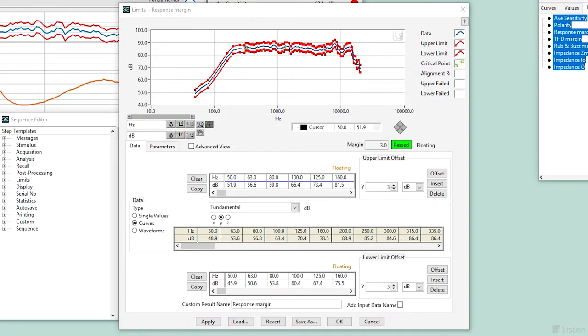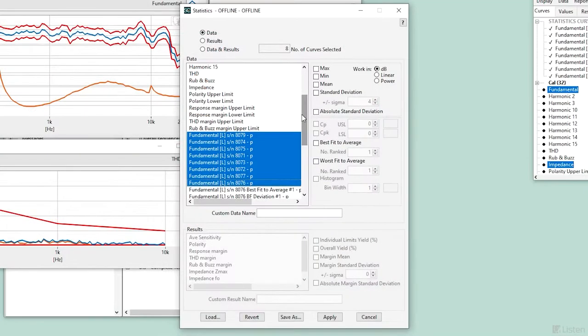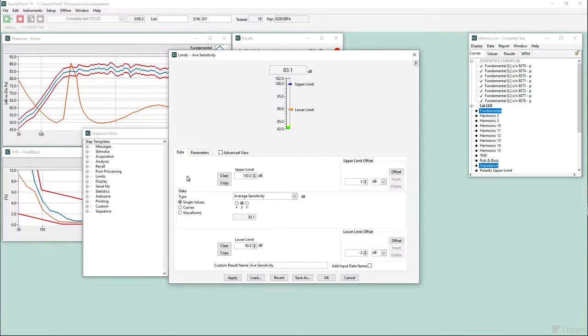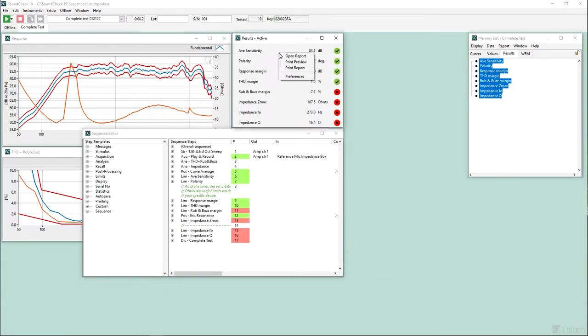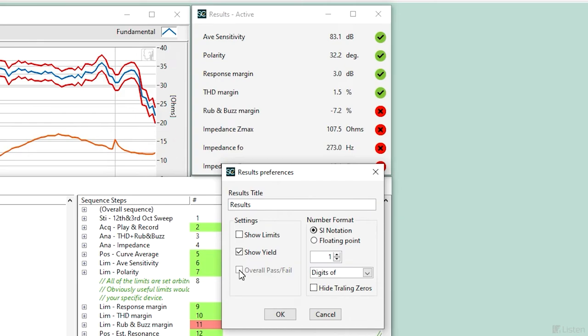Similarly, I can run statistics on a larger sample of curves, determine the mean, and use the average curve as the reference for a limit. For example, plus or minus 3 dB sigma or best fit to average. For single values like average sensitivity, the upper lower limit will also be a single value. A limits display can show the limits and the yield, or just display the overall pass and fail, which may be all the test operators concerned with.